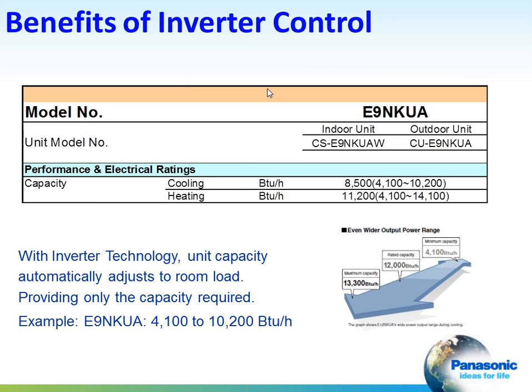Another benefit of inverter control is that we get better cooling capacity control, which provides better comfort. These units typically are controlled by the return air sensor, and as long as we're providing an acceptable discharge air temperature, we can range, in the example here of a 9,000 BTU system, anywhere from 4,100 BTUs to 10,200 BTUs in the cooling mode.